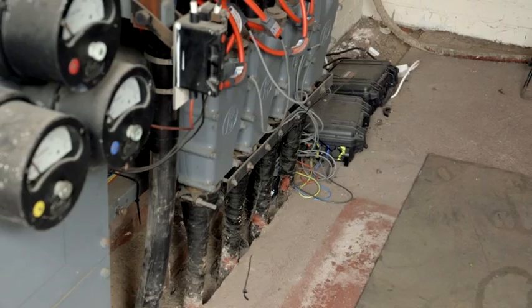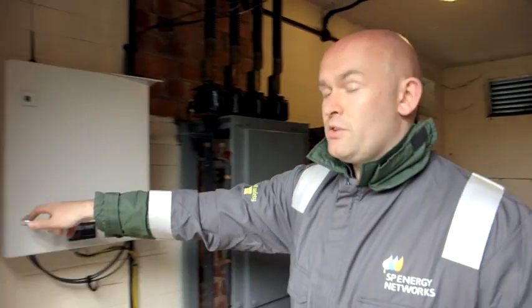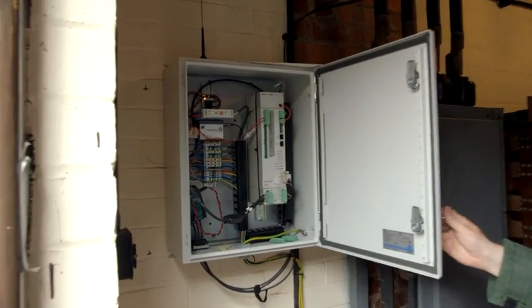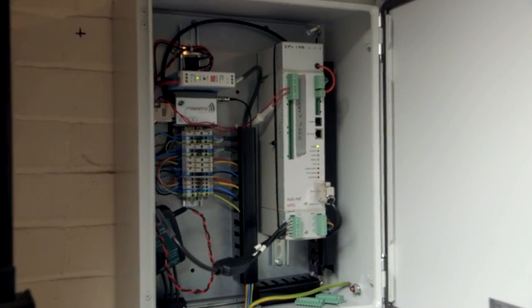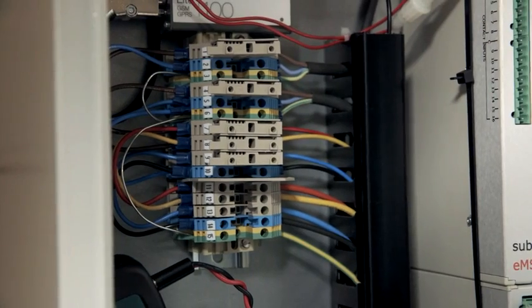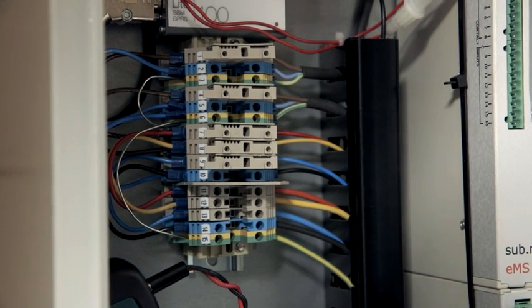Where this substation differs from our usual substation is that we've now added network monitors to it. What the monitor does is actually monitor the total demand on the transformer of the substation and compile that into a daily report, which is communicated to my computer wirelessly. The reports produced by the monitoring equipment enable me to see the exact demand profile for this substation, and more importantly, to see if our substation and electricity network are meeting the demands of the village.